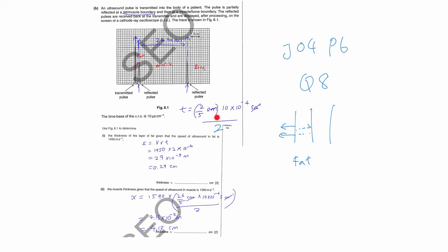So you must divide by 2. Then you take the speed — 1,450 — and multiply by this value. After you calculate this to be 2 microseconds, you get the thickness.